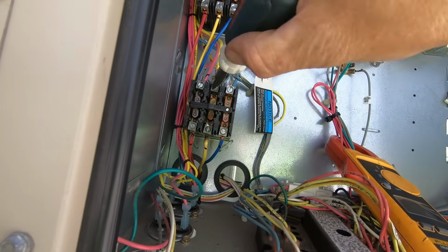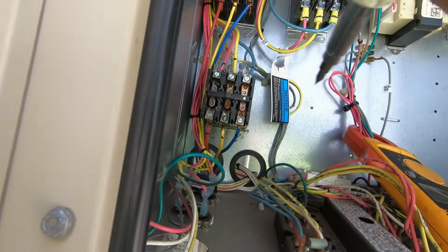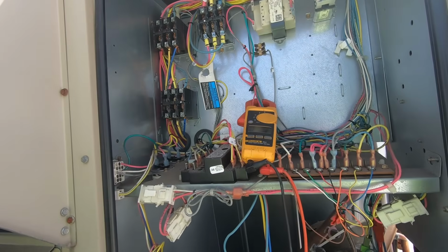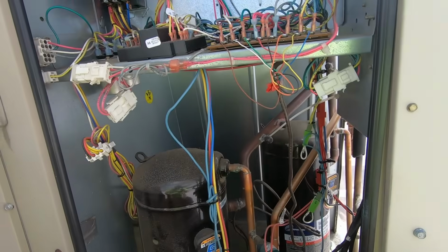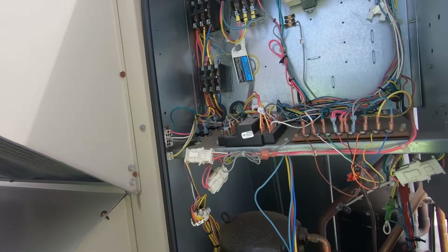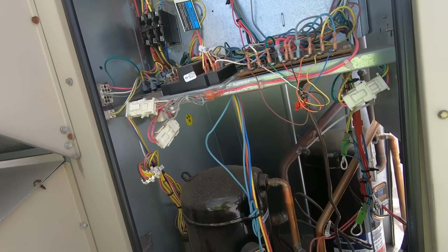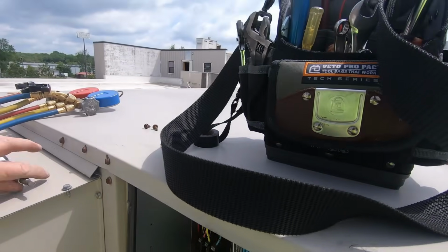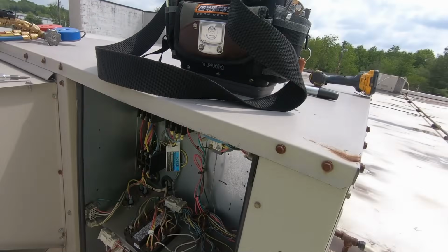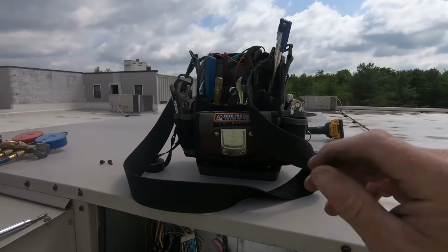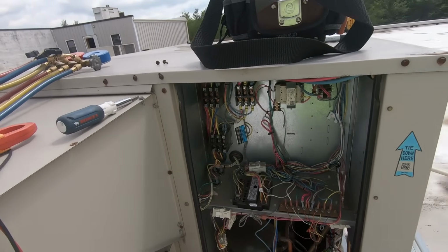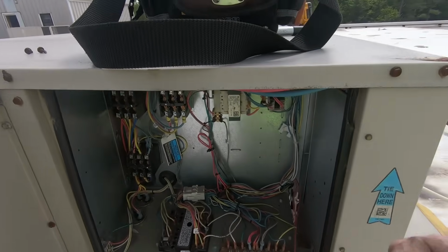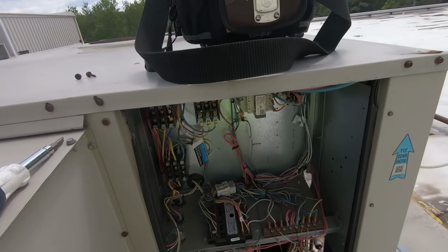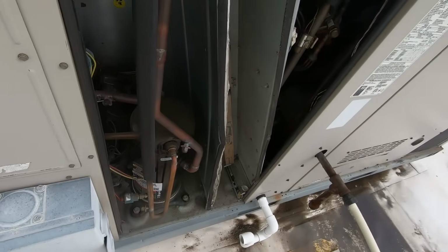And not extremely loose, but they've been so heated. What I'm going to do is only jump out Y1 and see which contactor pulls in. Blower is good, belt needs replaced, filters need replaced, coils are going to get cleaned, heat exchangers good. So I'm going to jump out just Y1 and see if it's that contactor that pulls in, then we'll evaluate from there. Okay, I'm all jumped out.